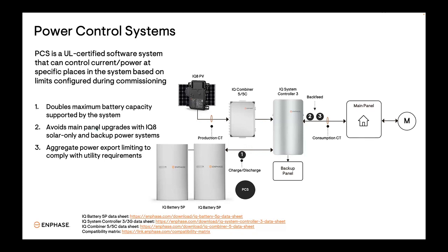Now, another big benefit is what I mentioned earlier, avoiding main panel upgrades. So for that, the consumption CT is going to be located between the system controller and the main service panel. So we can monitor electrical current flowing back into the main panel, and we can ensure that the combined current of PV and batteries will never exceed whatever is safe for that main service panel. Now, if you overdo this, obviously you could potentially limit the energy production of the system.